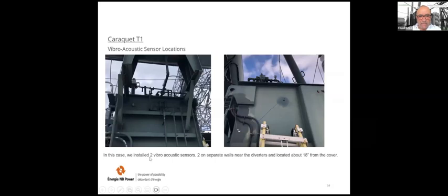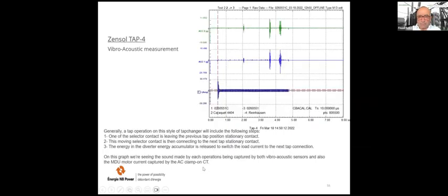In this case, we installed 2 vibroacoustic sensors, 2 on separate walls near the diverters and located about 18 inches from the cover. In fact, they have used 2 just to be sure that they got exactly the same result. But as I told you in the beginning of the presentation, we need only 1. And here, this confirms exactly what I told you. Here you have the 2 accelerometers. So in fact, the analysis is done with the 1 is enough.